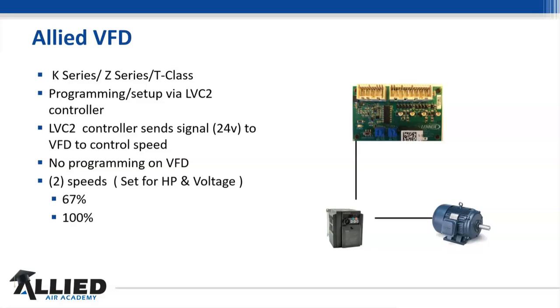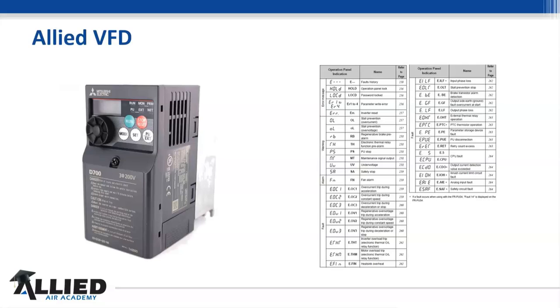But one of the best things you can do is go on to Mitsubishi's website and download the manual for this, and that way you'll have it. But that's the reason why we install these things: for 2-speed operation on the fan, power savings, and then there's some on this board. I'm going to show you how to troubleshoot this board in just a few moments. But you may come up with some codes and things of that nature. We have some of the codes in our instruction as it pertains to our programming. That's why I say go ahead to our site plus Mitsubishi's and get the full manual on this. It'll have the full set of codes, and it'll help you in the long run knowing these things, because we're not the only ones that you have.